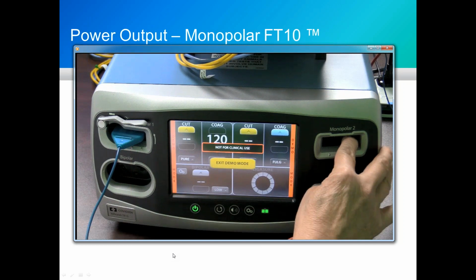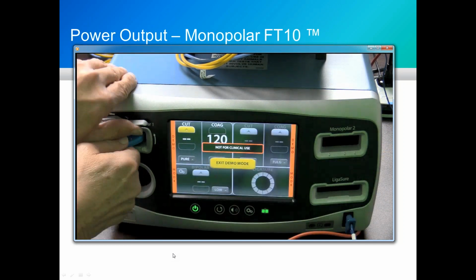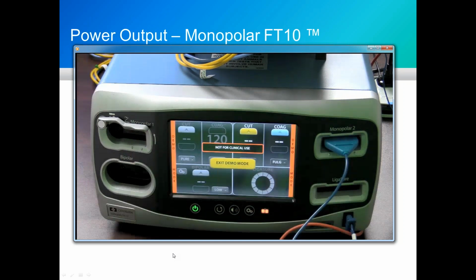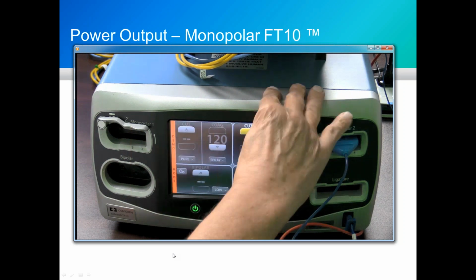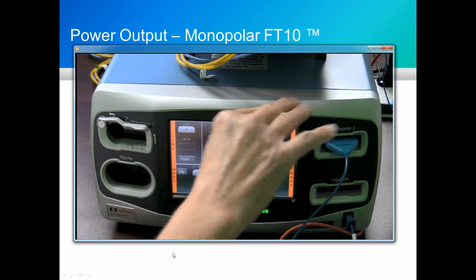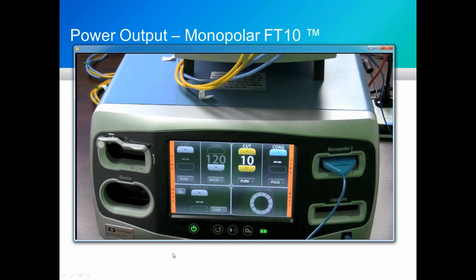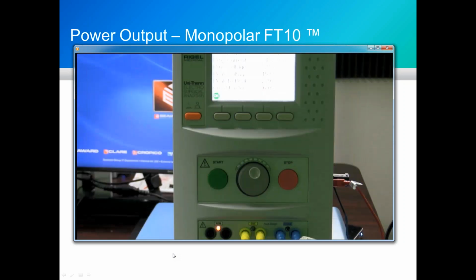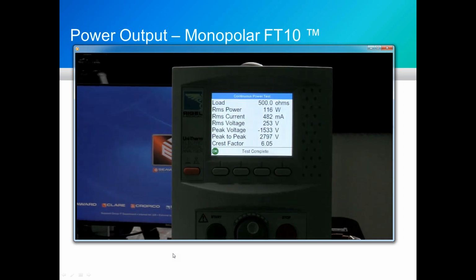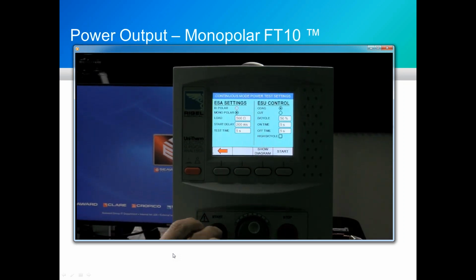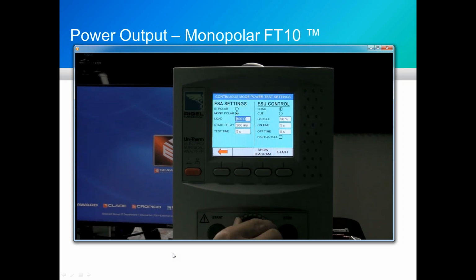So first, with the foot switch adapter, notice there's a small micro switch on monopolar 2, and that switch has to be engaged before that quadrant of the display will become live. I'm setting it for 10 watts continuous. We're going to change our load resistance to the specified 300 ohms. And I'm selecting cut.